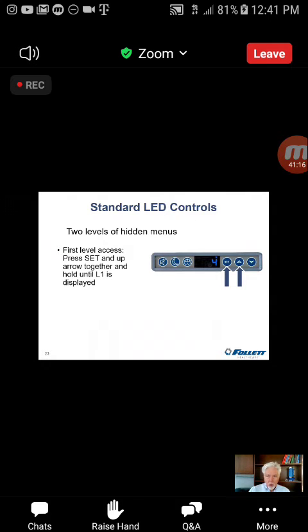Put your fingers there, hold, wait, and what's going to happen is L1 will come in the display. You are now in level 1 of the hidden menus. If you need to get to level 2, which has even higher advanced settings, you have to release it. You can't just keep your fingers there, because nothing will happen. Withdraw your fingers, do it again, wait, and you'll see L2 come in the display as long as L1 is still being displayed. Then it jumps to level 2. You're now in the second level of hidden menus. So that's going to bring us to our next video that goes through some of those controller settings.